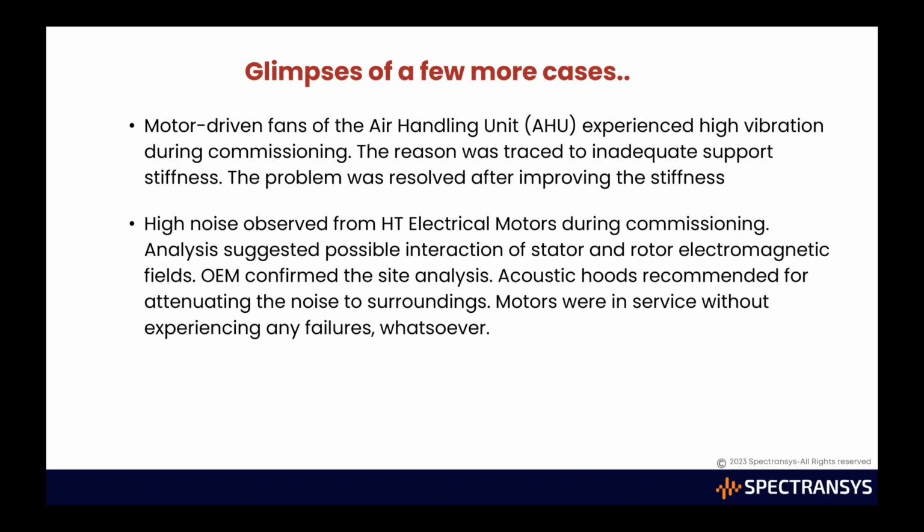Now these are all brand new machines which were brought to the site for installation. How can they have high unbalance problems and structural rigidity problems? So some homework was not properly carried out by the design, engineering and manufacturing teams at their works.